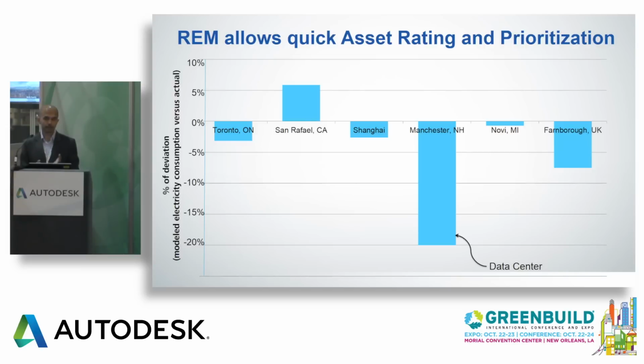One of our big customers, a construction company, saw a similar chart and realized $55,000 worth of savings when they noticed this deviation. They sent somebody on site and found that the heating and cooling were fighting against each other because the dead band between the set points wasn't set correctly—without doing an expensive audit. An audit would have cost them $10,000.